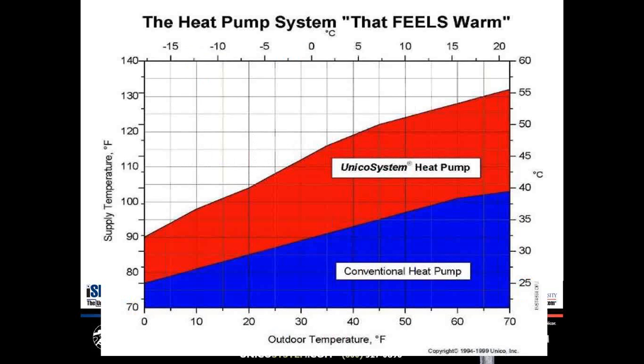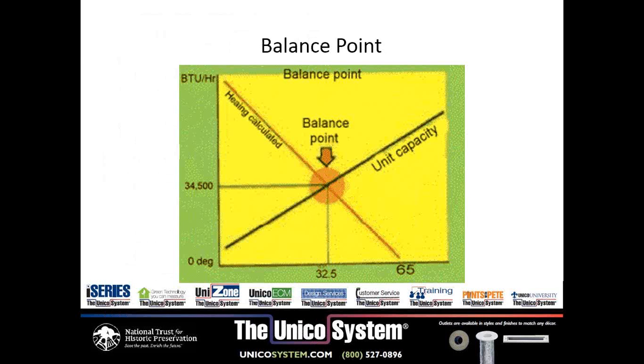Again, our heat pumps put out warmer temperatures than a conventional heat pump. All heat pumps do have a thing called a balance point, and basically what a balance point means is that as the temperatures get colder, the system produces less heat. So at some point, and that's going to be determined not only by your equipment, but what kind of house you have. If you have an old drafty house, you're going to have a much higher balance point than with a new construction house. And below that balance point, you need to fill that up with auxiliary or emergency heat. So typically, we set up a heat pump. In my case, I set up a heat pump for about 30-degree outside temperature. Below that, the heat pump shuts off, and the boiler comes on. So I get the best of all worlds in terms of energy efficiency.